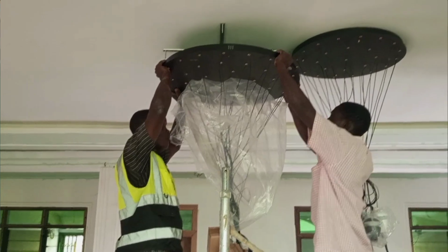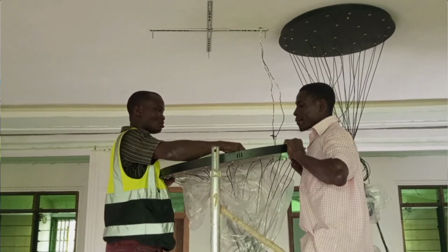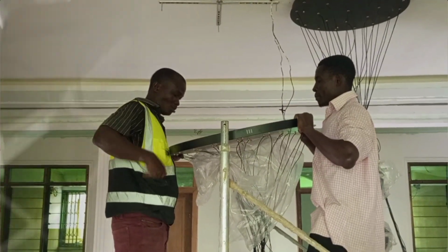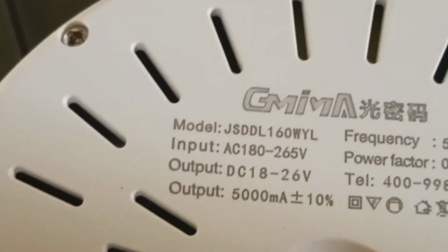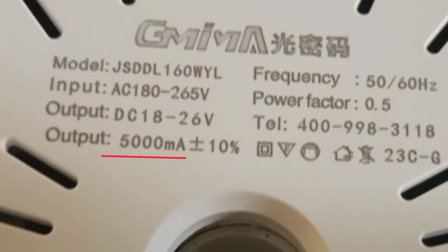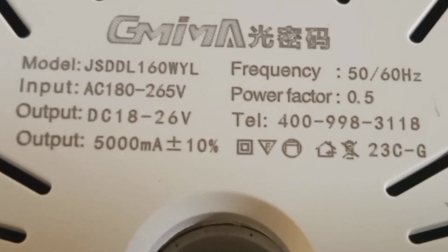All right, so the information about how much the lamp consumes can be found. This is an LED lamp, so we can find that information on the LED driver. Okay, so let's go and look at that. So here, this is the LED driver that powers this chandelier. If you look here, we are looking out for current. If you find current, it's okay because the circuit breakers we'll be using are rated in amps already.